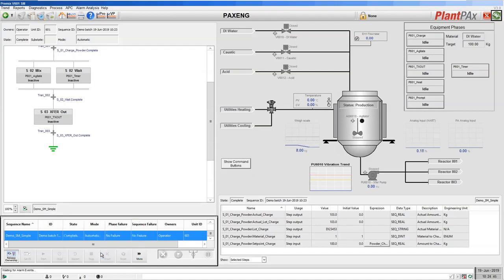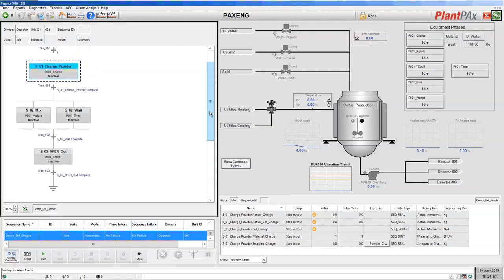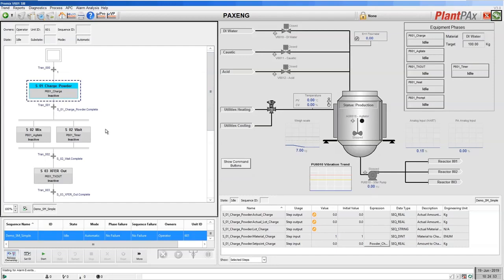Our sequence is now complete. We can reset that sequence back to idle from the control. With these ActiveX controls you have full control over the execution: you can hold the sequence as it's running and it will go into hold, then you can restart it, stop it, or abort it. You can also take manual control of steps — manually start and stop them, or change and go back to a previous step and run from that point if you wish to recover.